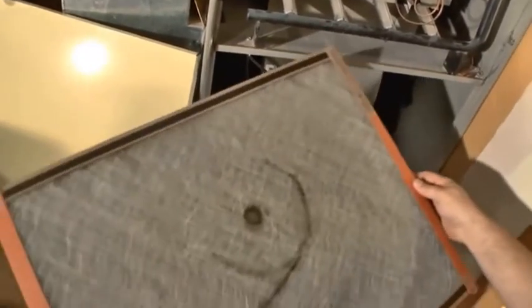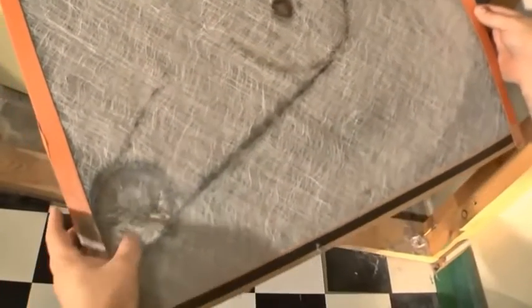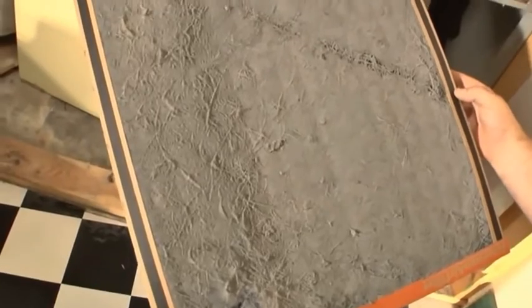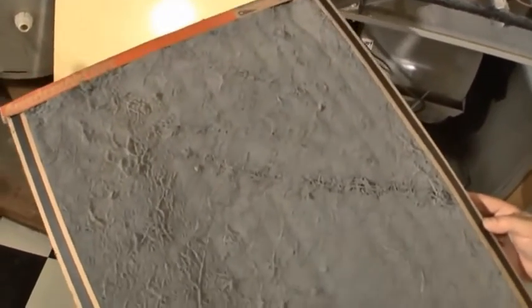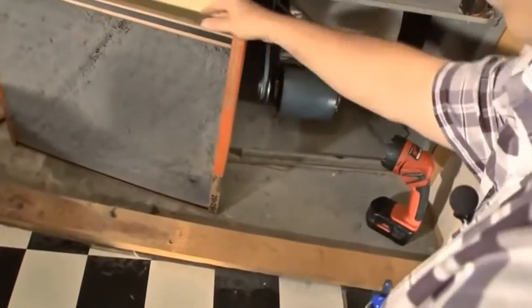This is somewhat common when there are no supports to hold the filter in place. You can see all the fiberglass shavings that have collected in the motor from rubbing up against the filter. So we'll go ahead and pull that filter out. You can actually see the imprint where the belt has been riding on that, and all this fiberglass is gone. And then you can see how dirty this filter is. This is pretty dirty. That's probably one of the reasons why it got sucked into the fan, from all the dirt that collected and plugged up the filter, so it created more of a suction to the fan.